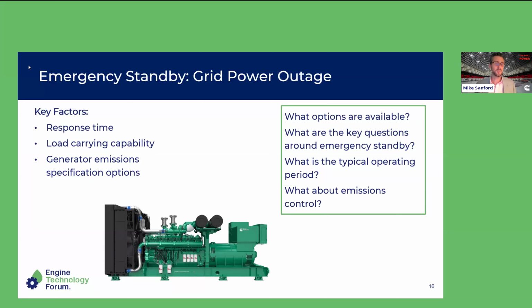The sophisticated controls on site call the generators to turn on and begin spinning up. Once they're available and able to provide load to the site, the mechanisms in the gear physically move the connections through a series of circuit breakers, typically switching the path from the normal source of power to the emergency circuit, which is usually the generator sets on site. This happens very rapidly, typically in fewer than 10 seconds overall, from the time the normal power source fails to the time the generator sets are online.